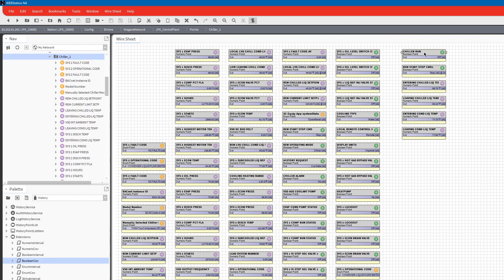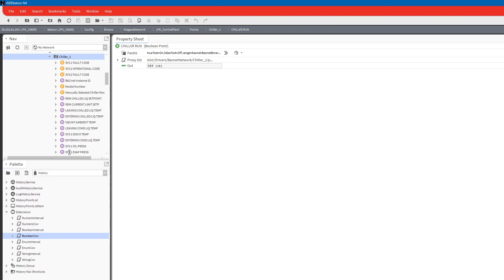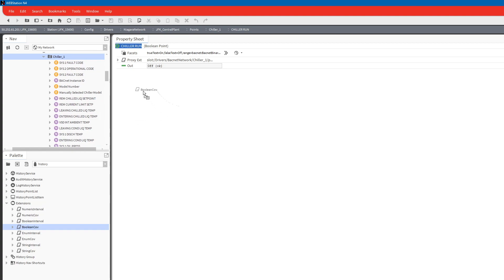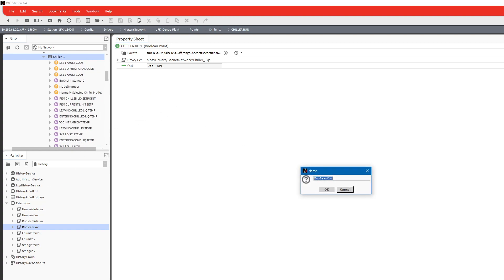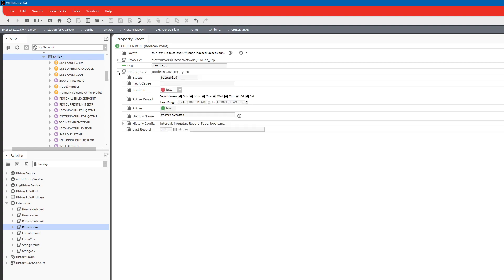The first one I want to do is this chiller run, so we're going to go into the properties. Over here on my side pallet I have histories and then I have extensions expanded. For this one we're going to want to do a boolean conversion, basically meaning that every time it changes state it's going to take that log. We can name this history, have it go out and grab the name itself, we can do parent parent or parent dot parent dot parent dot name so that it'll say for instance chiller one chiller run for the point name.